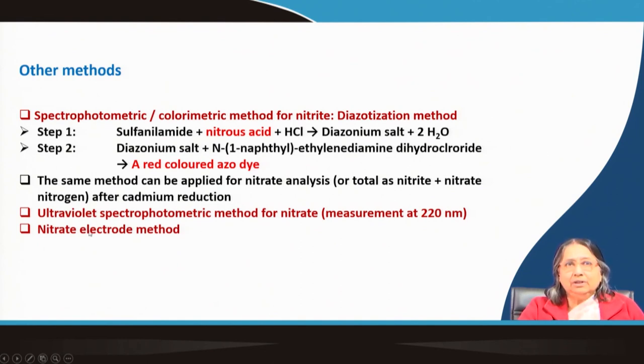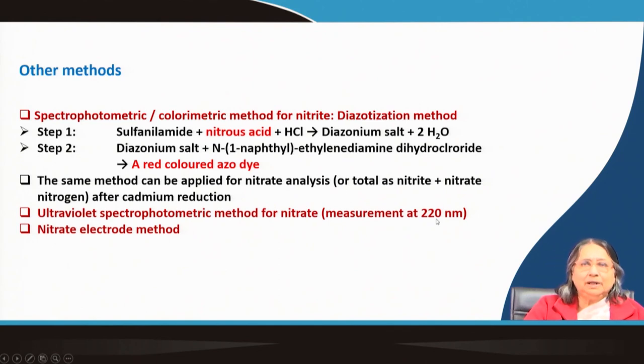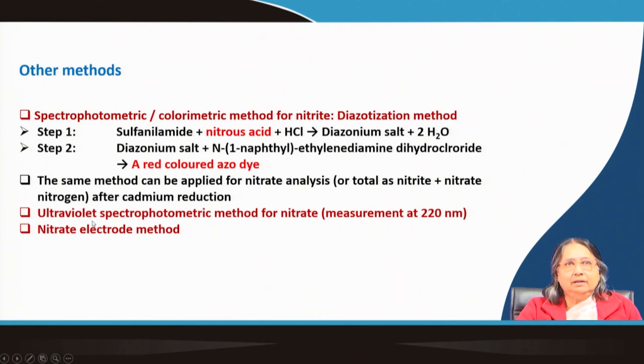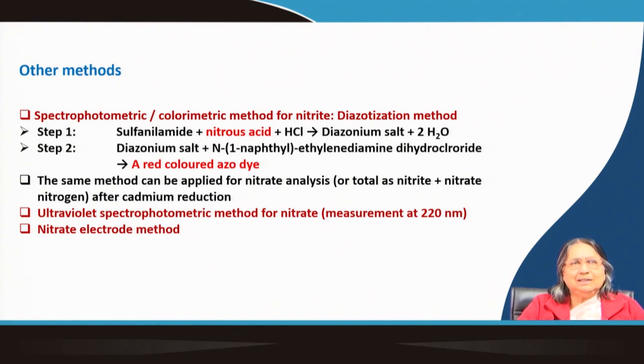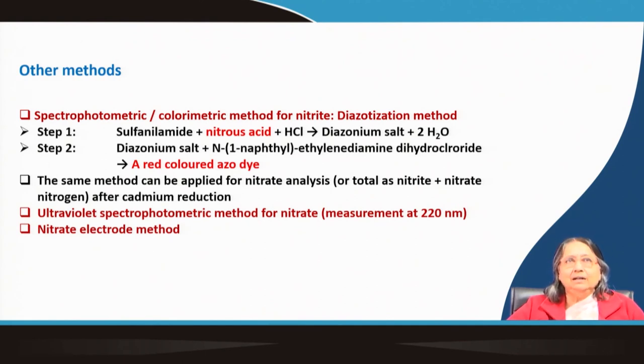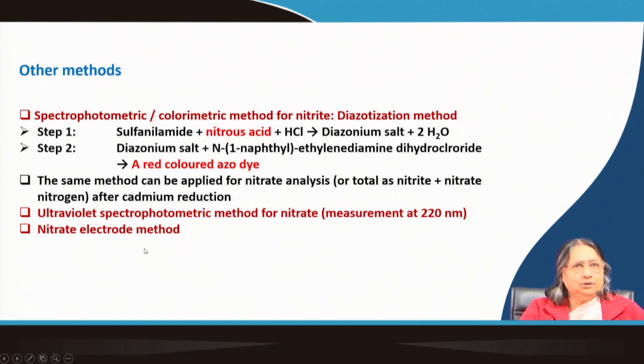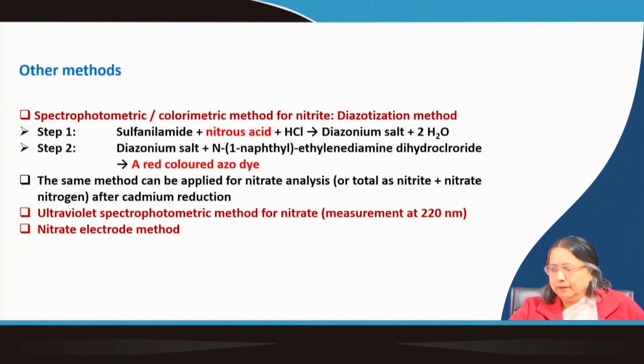Another method is UV spectrophotometry at 220 nanometers, a simple but less reliable method requiring a UV-visible spectrophotometer, which is costlier than a visible-only instrument. A nitrate electrode is also available — very user-friendly, requiring only calibration and measurement, though its shelf life is only about one to two years and it is relatively costly.